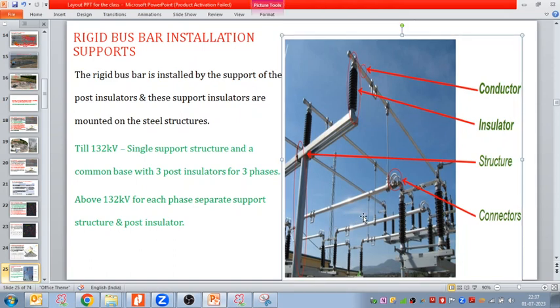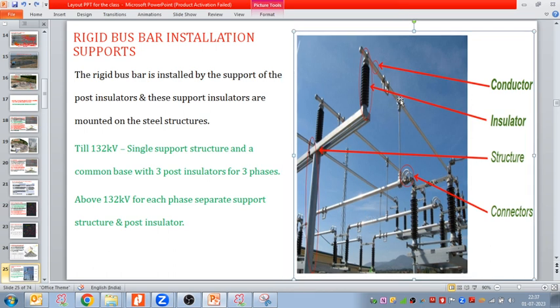For the equipment, we take the drop from the bus bar to the equipment here. This loop is for the earthing of this bus bar - to fix the earthing clamp, the portable earthing rod, we place it here because the OD of this tube is high, so we cannot easily fix the portable earthing with the conductor. So here we can place that - this loop provides a point for the earthing.